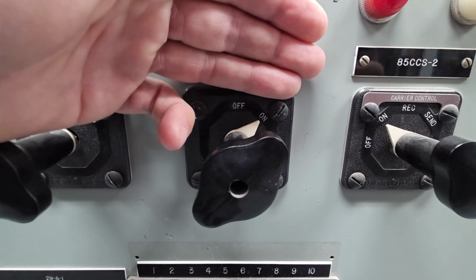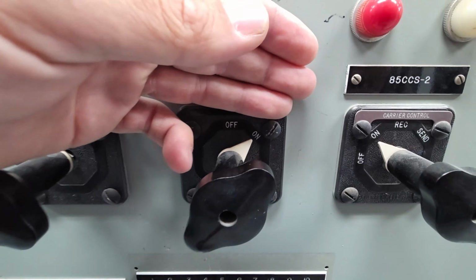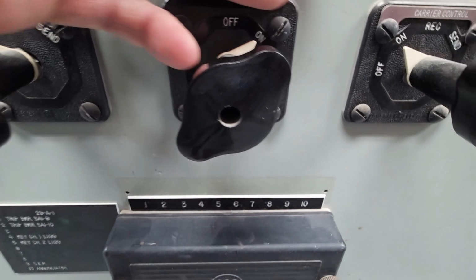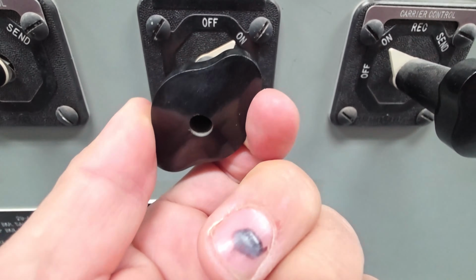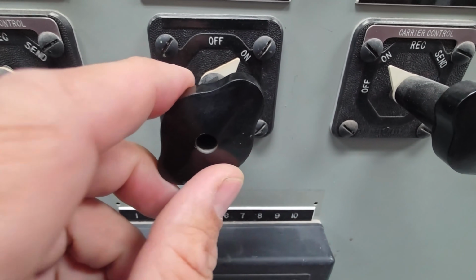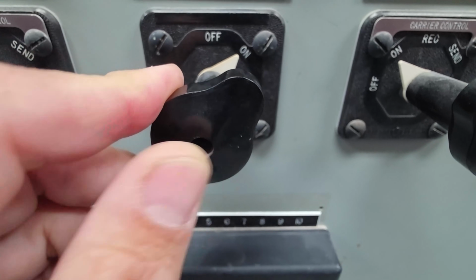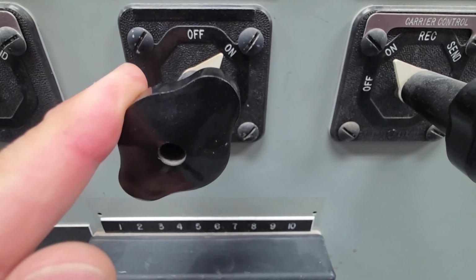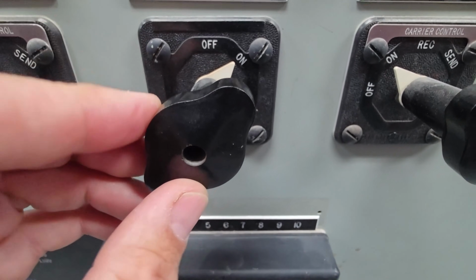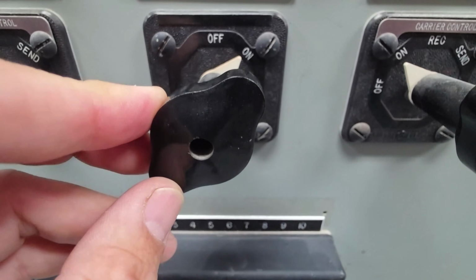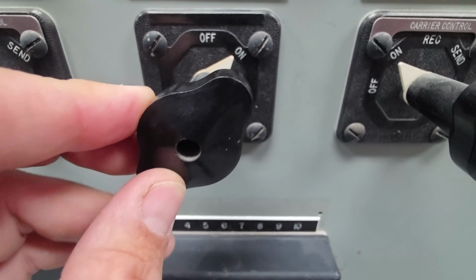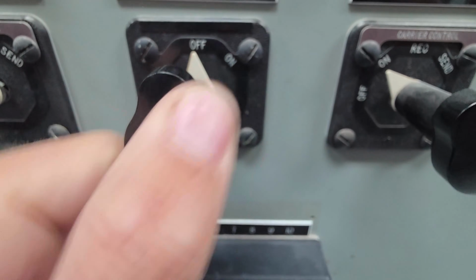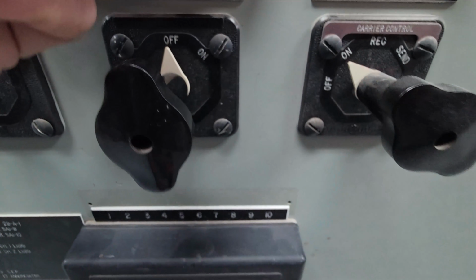Reclosing is currently on, meaning if the line trips, it will automatically close back in. We want to turn that off. It's a simple task, we just take that handle. I always say when doing switching, find your location, and right before moving the switch, confirm again, always double check. So I'm confirming the line number again, making sure we're at the right location, and now we have our reclosing shut off.